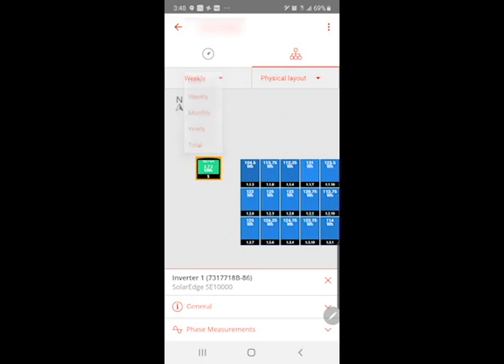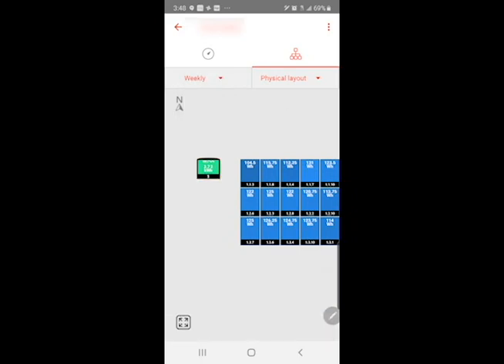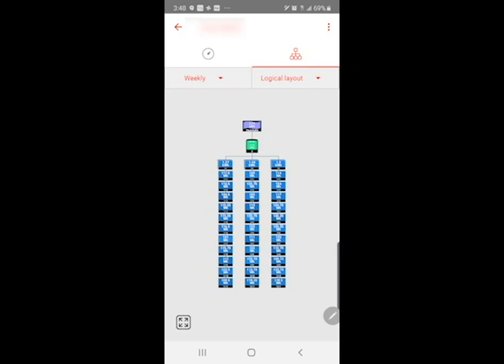Another great way to inspect your system is looking from the physical layout to the logical layout. This is electrically how all your modules are connected on the roof and going into the inverter. We can diagnose remotely if there's a problem with an entire string, or if it's maybe just one module or just one optimizer. So this is a pretty powerful tool.